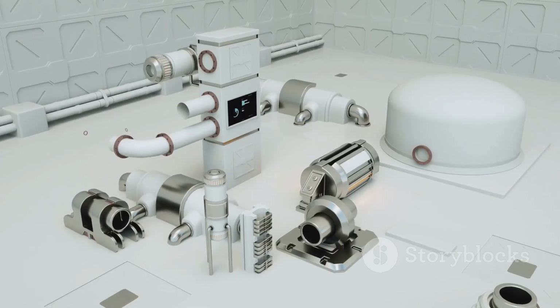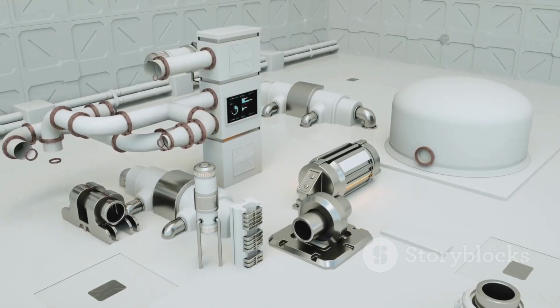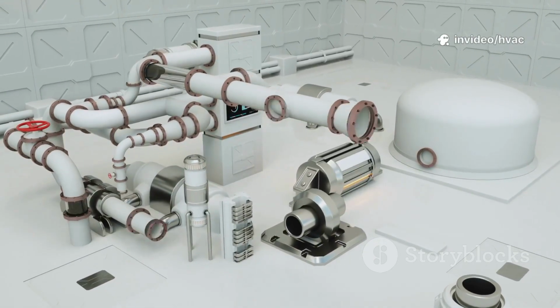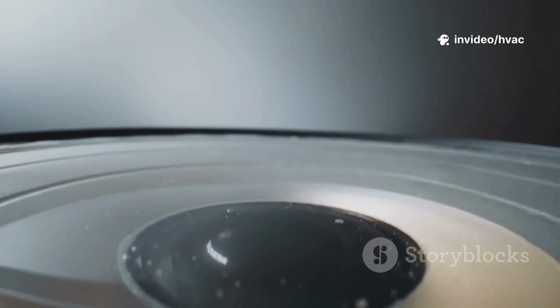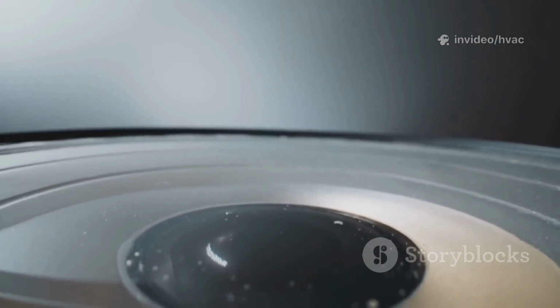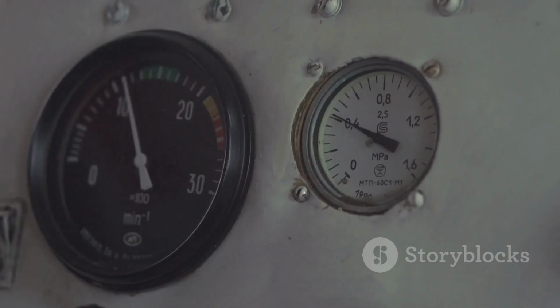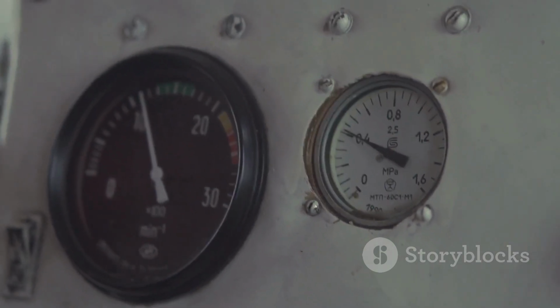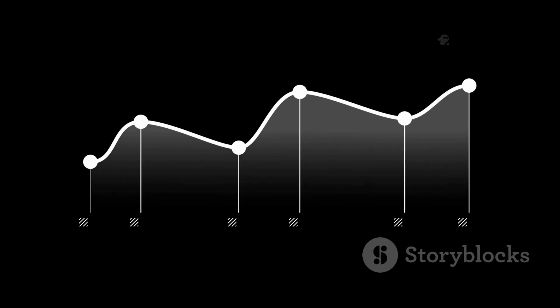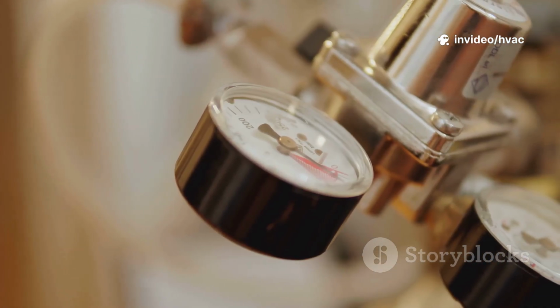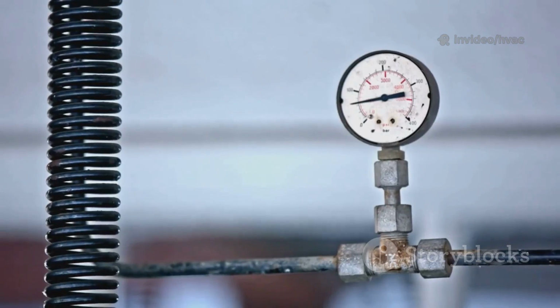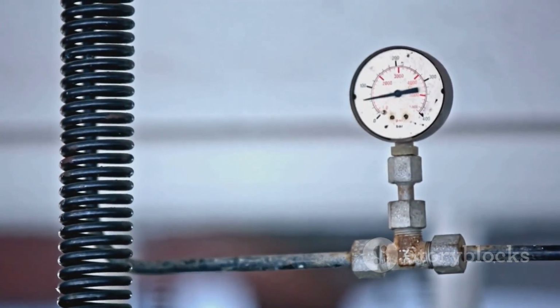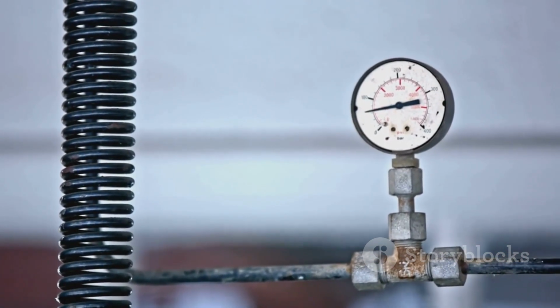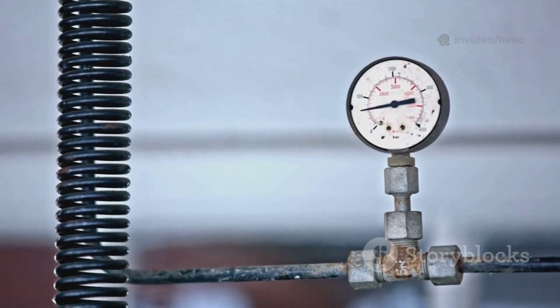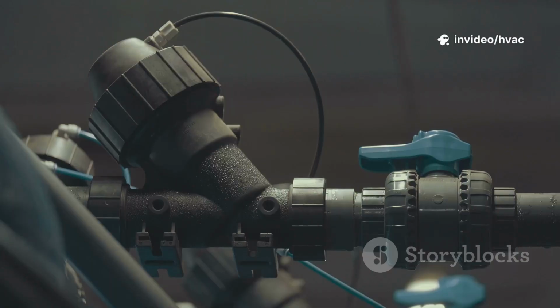Imagine the pressure in the main building pipe suddenly increases. This higher pressure pushes against the diaphragm inside the PICV's regulator section. The diaphragm moves against its spring and partially closes an internal passage, absorbing this extra pressure. As a result, the pressure reaching the control valve section remains steady and constant. The pressure difference across the control valve, the part that actually meters the flow, does not change, even though the main system pressure went up. Because the pressure drop across the control valve is constant, the flow rate will also remain constant, as long as the control valve position does not change. This is the pressure-independent feature in action.